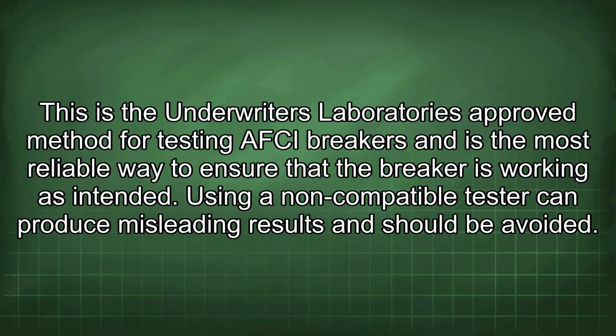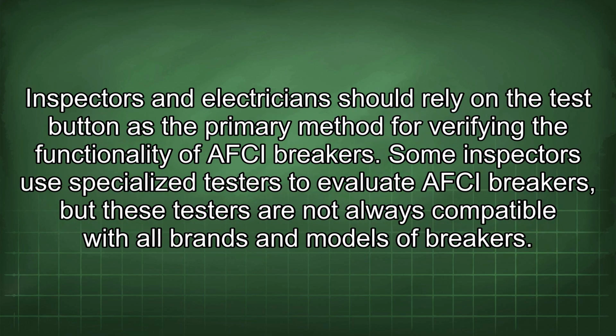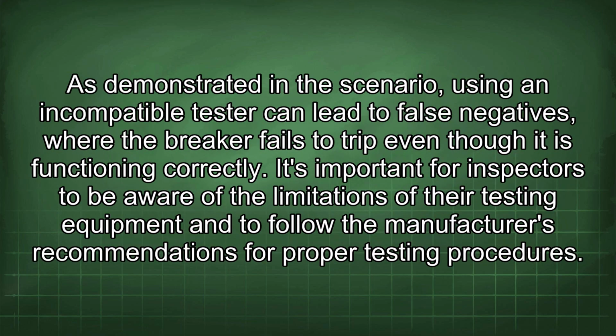Using a non-compatible tester can produce misleading results and should be avoided. Inspectors and electricians should rely on the test button as the primary method for verifying the functionality of AFCI breakers. Some inspectors use specialized testers to evaluate AFCI breakers, but these testers are not always compatible with all brands and models of breakers. As demonstrated in the scenario, using an incompatible tester can lead to false negatives, where the breaker fails to trip even though it is functioning correctly.